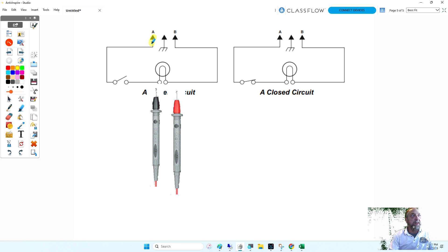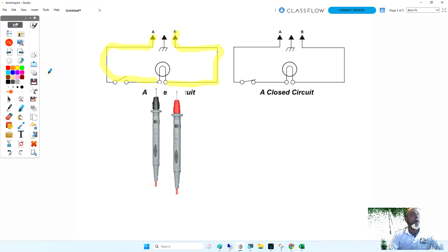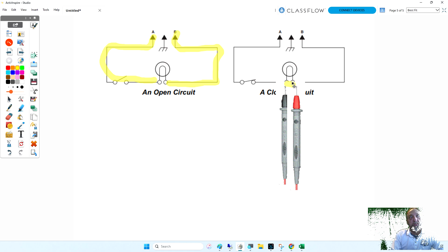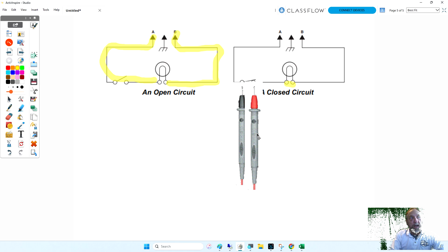When doing a voltage test, we're not testing the bulb, we're checking that the circuit is providing power to the bulb. Voltage checks out away from my meter leads, whereas an ohms test checks in between my meter leads. If I'm checking the switch, I'm just checking that one part.